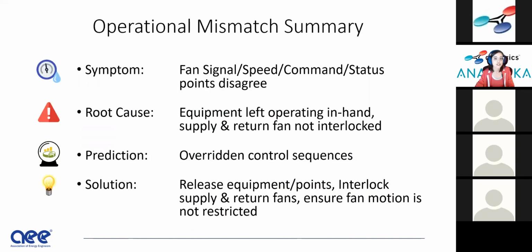So operational mismatch. Here we're talking about points that disagree. Sometimes the point itself might be bad, and we can help determine that too. This BAS point is out to lunch, and we need to repair it or replace it, the sensor point. Equipment operating in hand, that's the root cause here. Or the supply and return fan aren't properly interlocked, the controls. They should be interlocked so that you don't have pressurization issues.